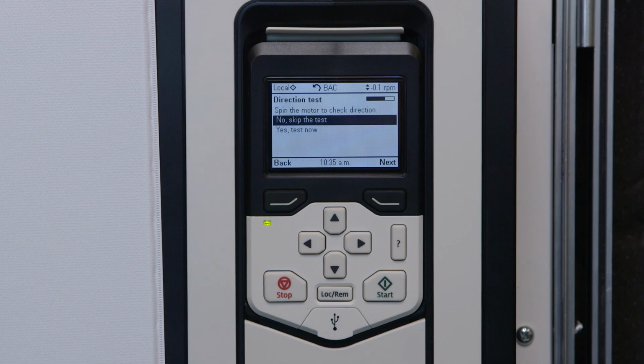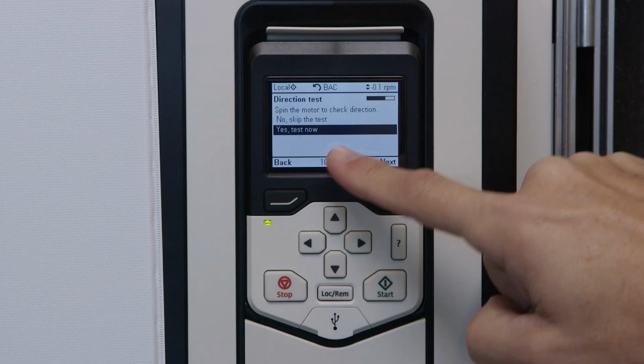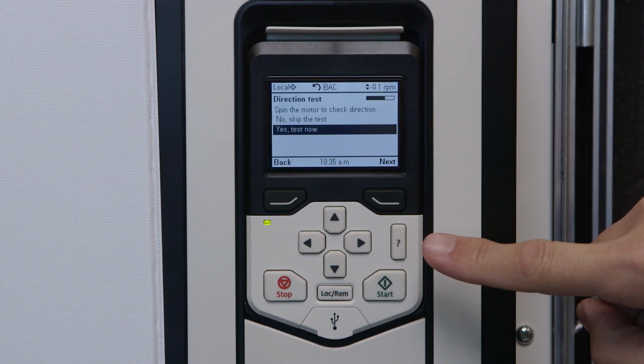Setup fan direction. When the ID run is completed successfully, you will need to check that the fan blades are clear from obstruction. Once this is confirmed, it's time to test the fan to ensure it's spinning in the right direction. To initiate the direction test, select the Yes Test Now option shown on the screen and press Next. Careful here to only press Next one time.